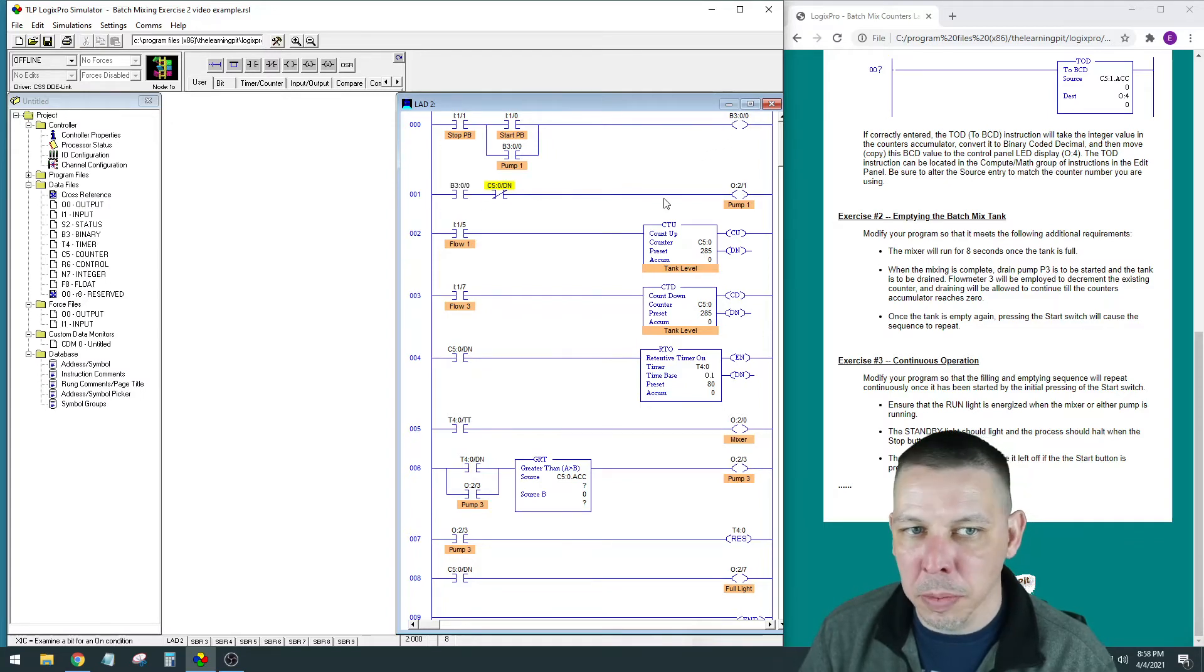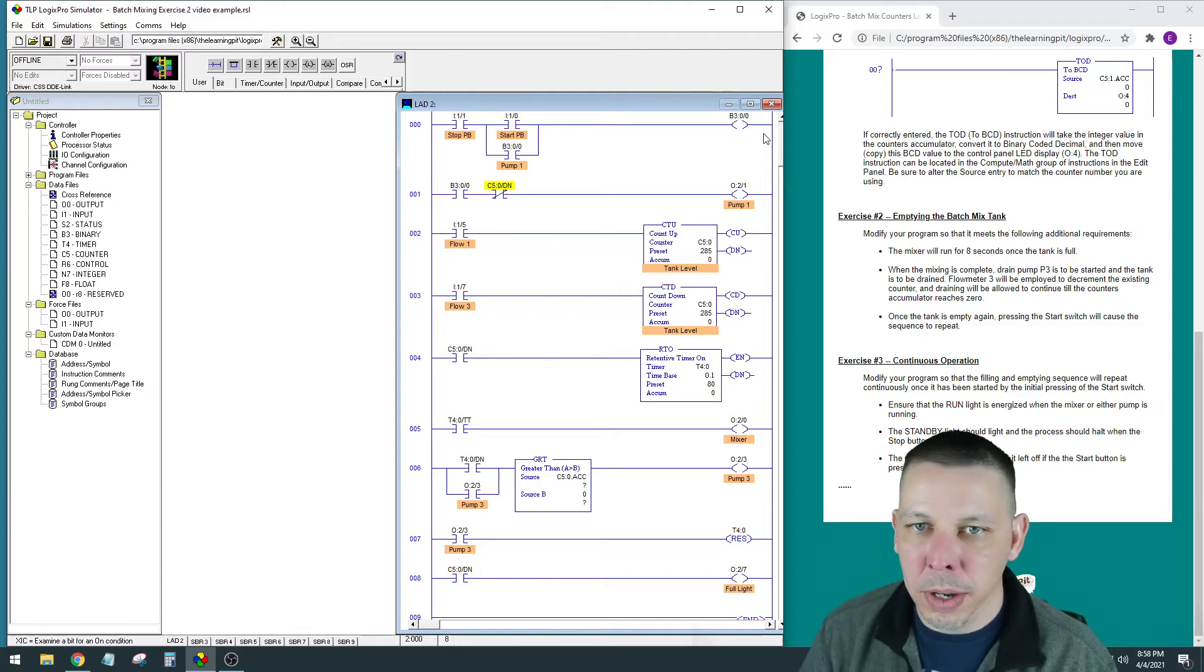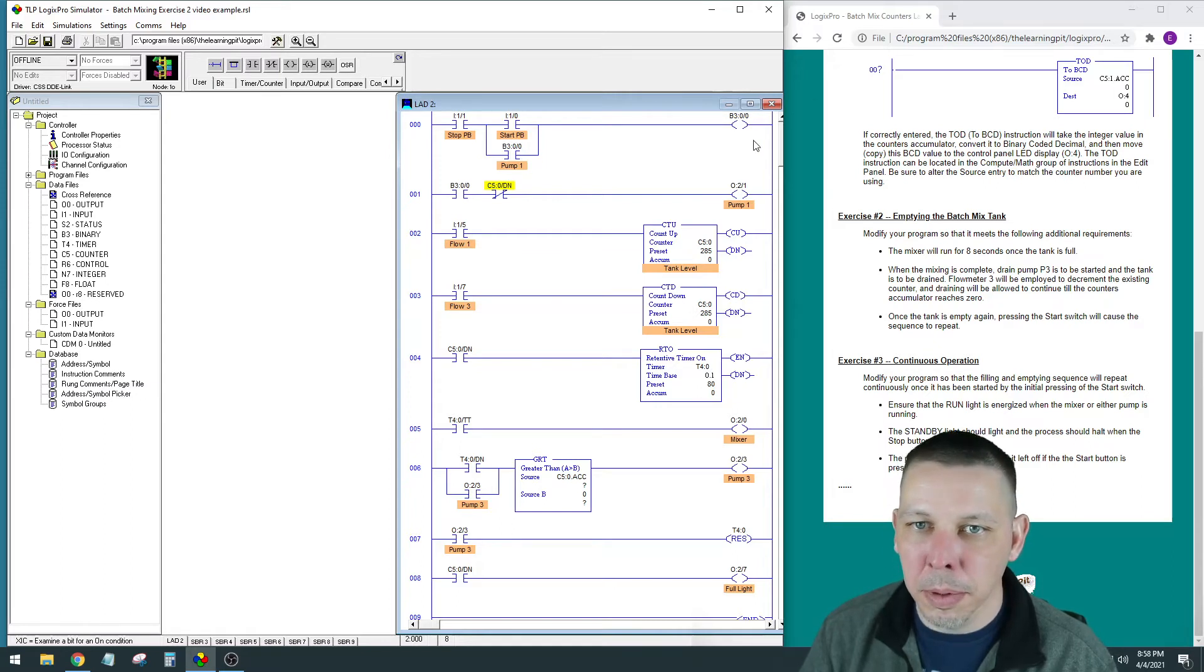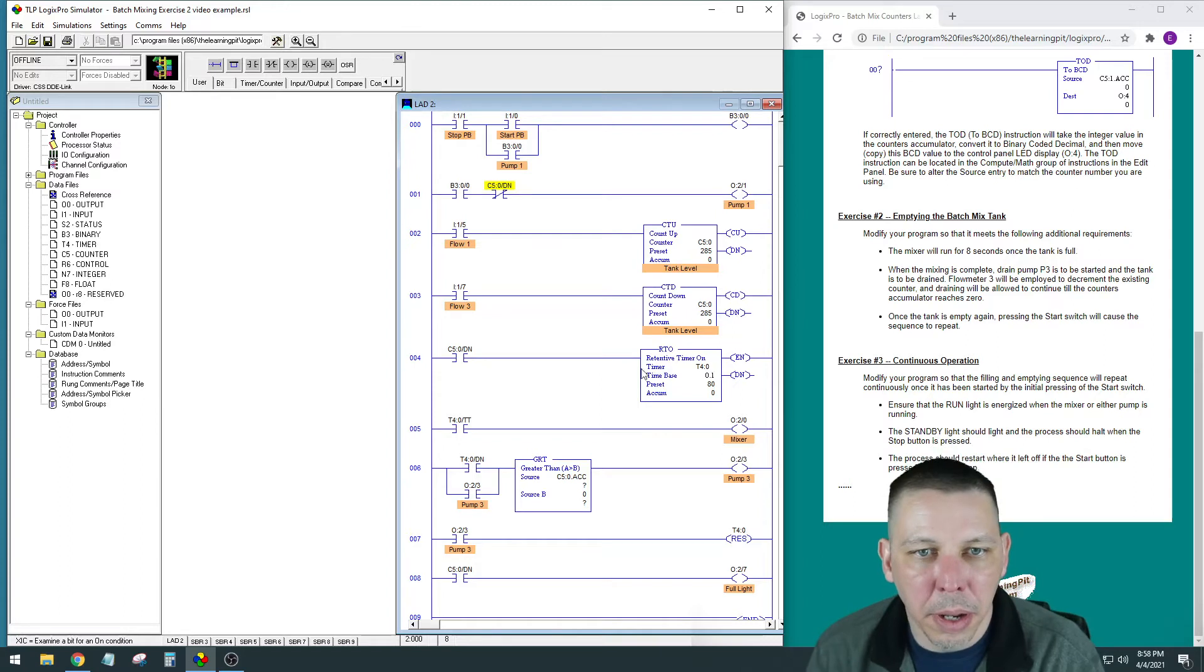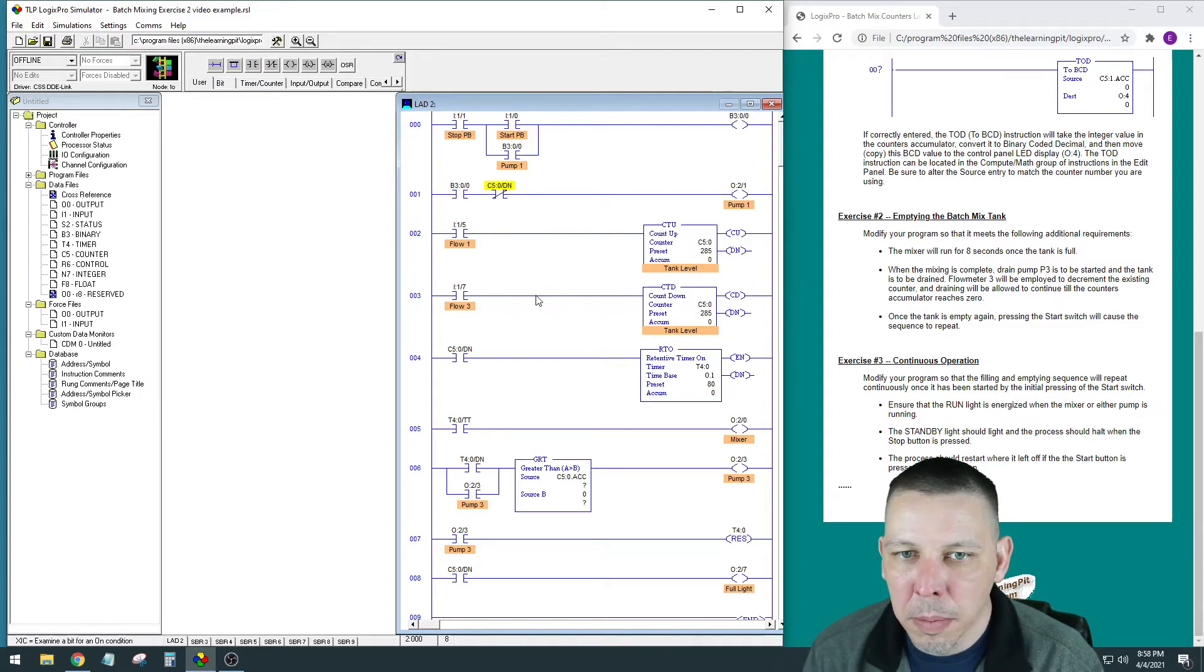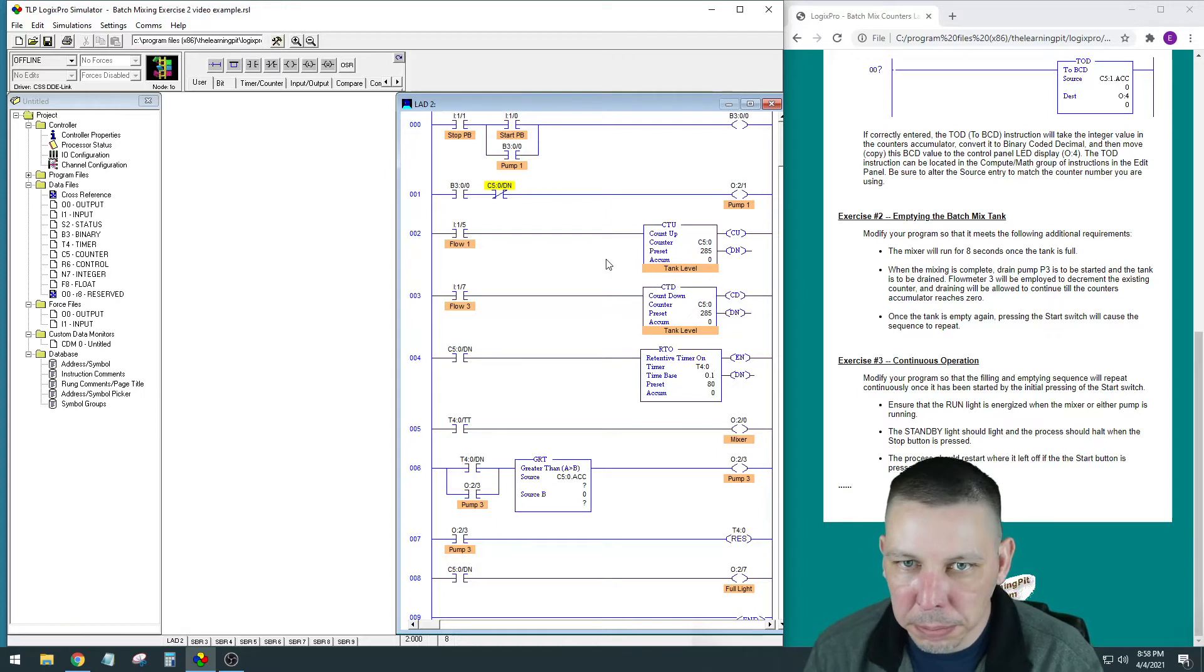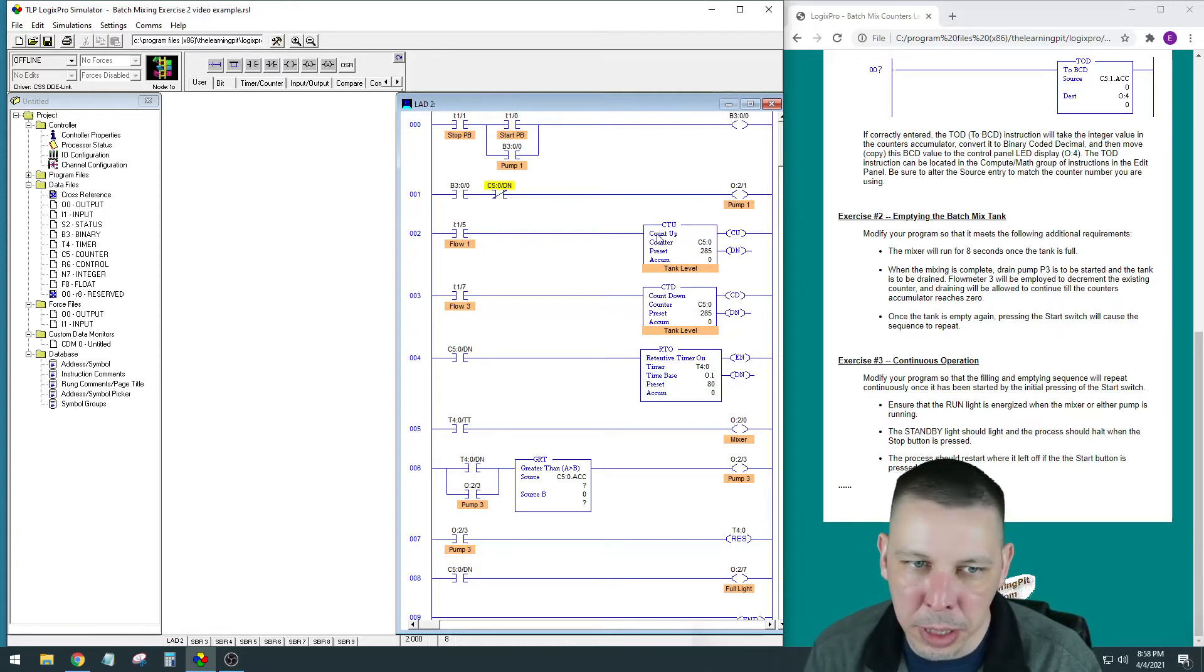I'm going to put a contact here. Now I just am going to address a lot of things in the beginning of these rungs based off that. So if you have start pressed, this will be energized and it'll allow the processes to run. If you hit stop, it'll kill power to that and it'll open up the rungs that you don't want to continue to run. The second rung, rung 2, you don't really need to interrupt because it only actuates when the flow meter has something flowing through it. So if you stop the pump, you're not going to have any flow through it, so the counter won't keep counting. Same with the countdown.